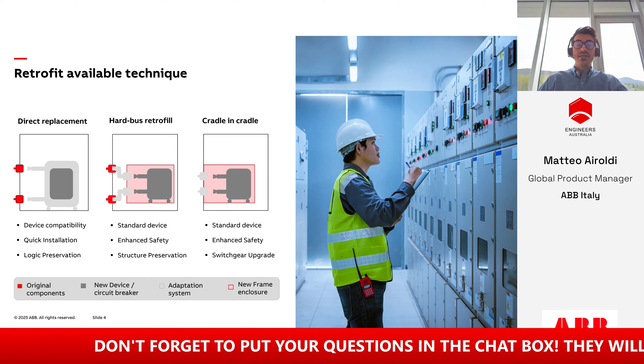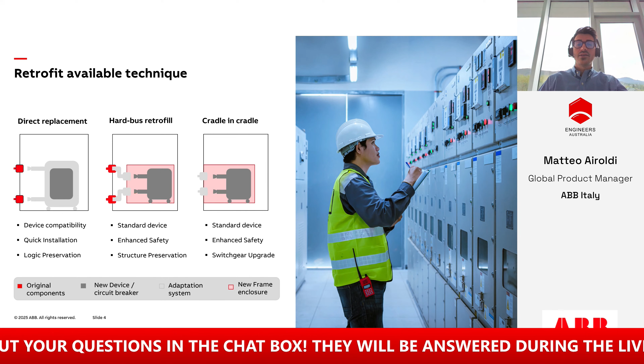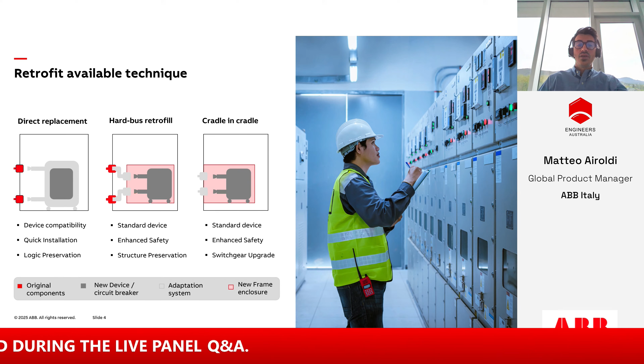This solution is ideal for installations where downtime must be minimized, such as data centers, hospitals, or continuous process industries. The second technique is the hard bus retrofit. In low voltage, this involves a new breaker with a custom design adaptation system that connects to the existing bus bars. In medium voltage, this same concept is known as One Fit, a standardized retrofit solution that ensures compatibility across a wide range of legacy panels. This method is used when direct replacement is not feasible, perhaps due to obsolete components or non-standard configurations.